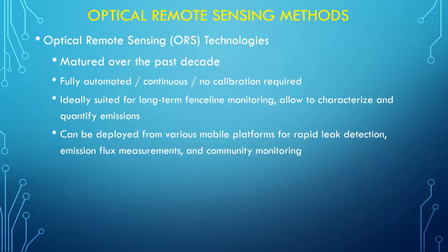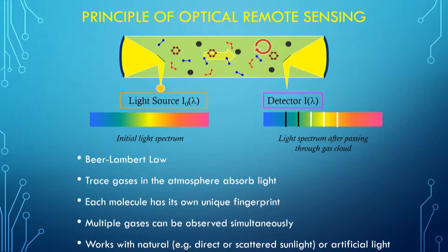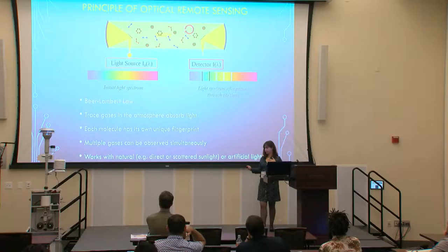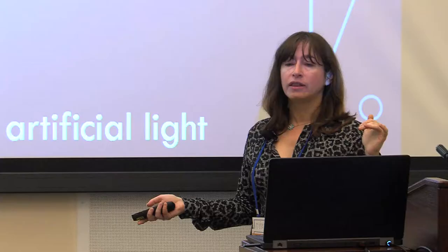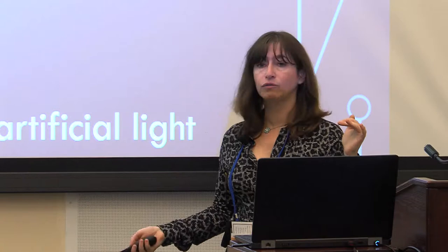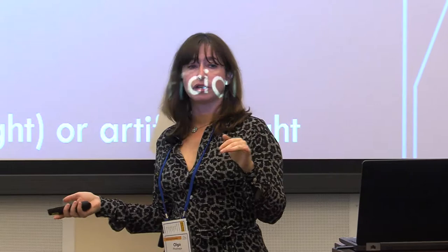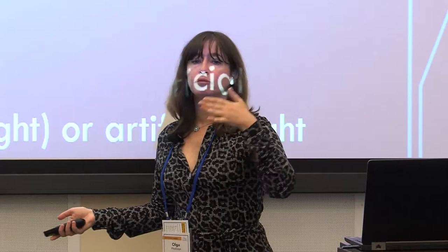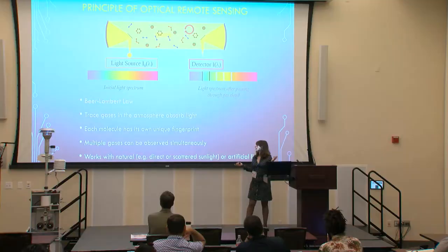It can also be deployed on a mobile platform. There are a multitude of optical remote sensing methods, but they all stem from the same principle — essentially the Beer-Lambert law, which says that light going through a medium is attenuated by the constituents in that medium, each in different wavelengths in a very unique way, so you can separate different pollutants simultaneously. Because each pollutant has a very unique fingerprint, you can conduct measurements very quickly for multiple pollutants. It works with direct sunlight, scattered sunlight, and artificial light, and depending on the molecules you want to measure, you select the optical remote sensing method and wavelength.